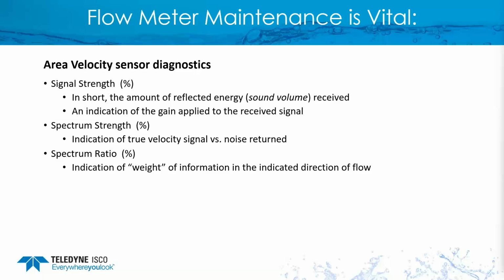If you're recording that information, usually what you're going to find is that the range is going to be between 40 and 60% is pretty average for the signal and spectrum strength. Because with a hearing aid, you don't have to have it turned all the way up to 100% to be able to hear something back. You maybe only have to turn it up 50%. That way you can get a good return signal.